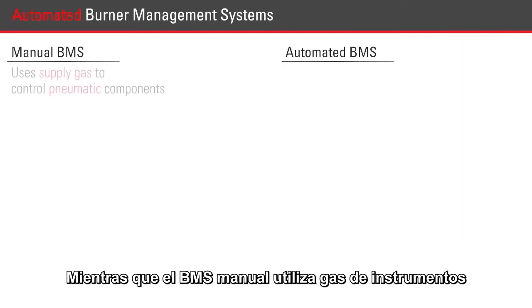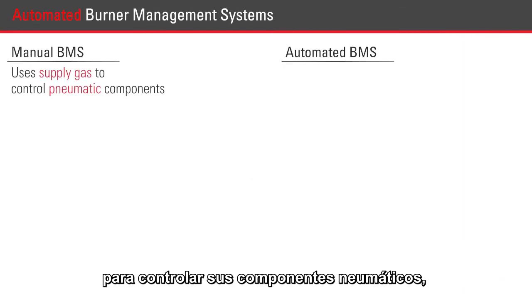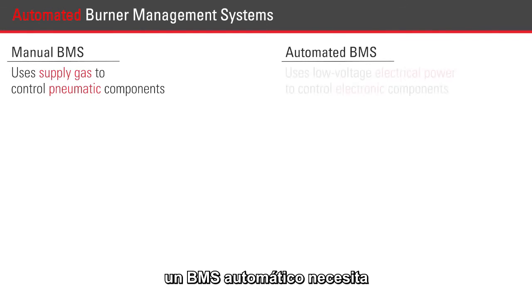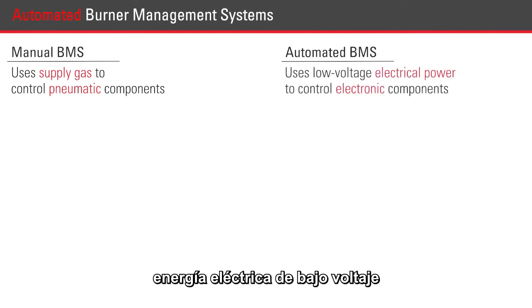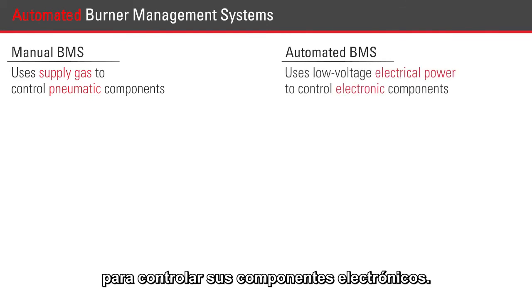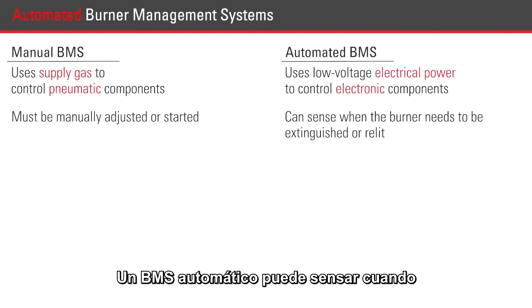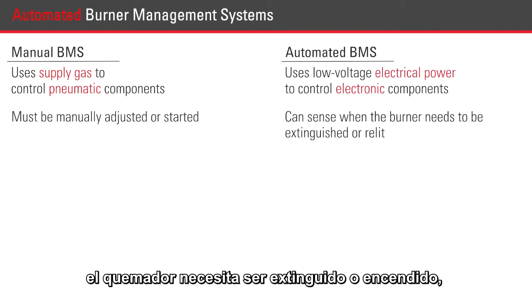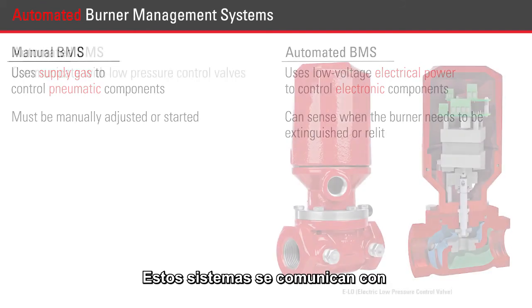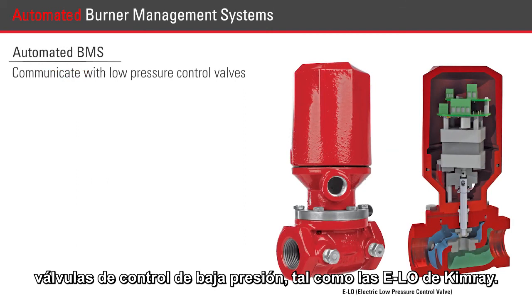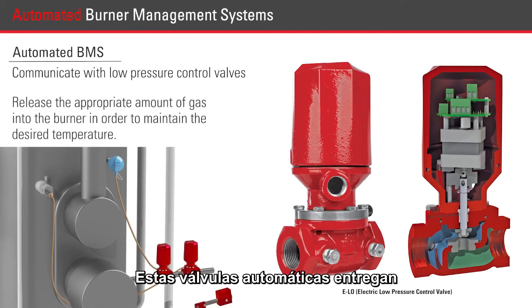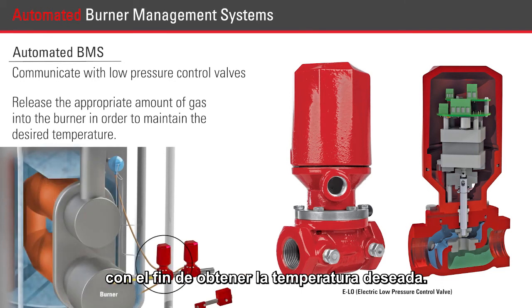While a manual BMS uses supply gas to control its pneumatic components, an automated BMS requires low-voltage electrical power to control its electronic components. An automated BMS can sense when the burner needs to be extinguished or relit and can complete this task automatically. These systems communicate with low-pressure control valves such as the Kimray ELO. These automated valves release the appropriate amount of gas into the burner in order to maintain the desired temperature.